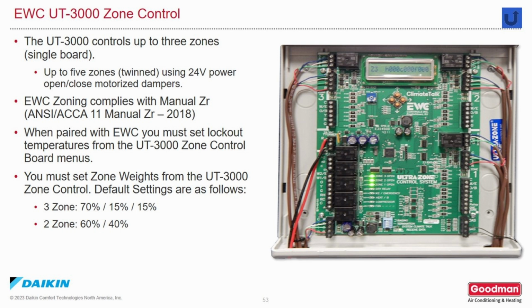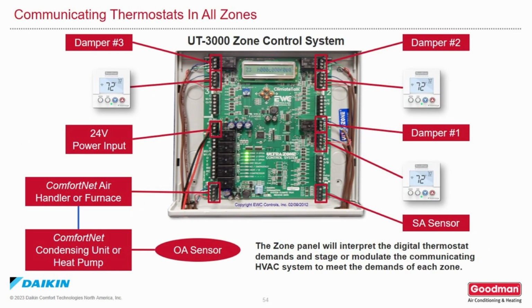The UT3000 zone control will control up to 3 zones from a single board and up to 5 zones from twinned boards using a 24-volt open and close motorized damper system. EWC zoning complies with the Manual ZR, ANSI ACCA 11 Manual ZR 2018. When paired with the EWC, you must set lockout temperatures from the UT3000 zone control board menus. You must set the zone weights from the UT3000 zone control. Default settings are as follows. The 3-zone is 70, 15, and 15%. 2-zone is 60, 40%.